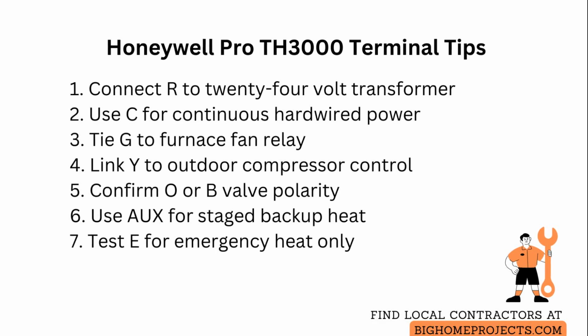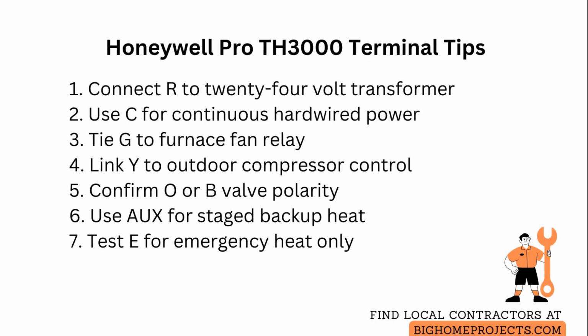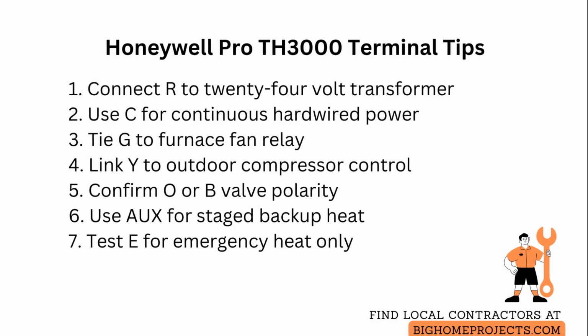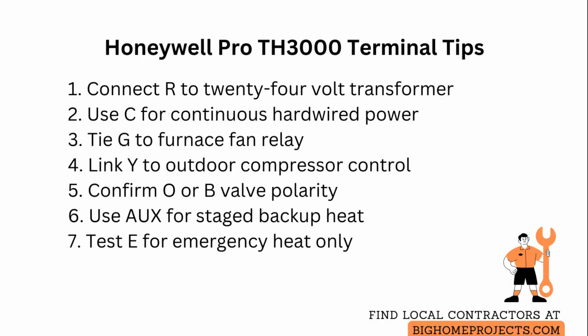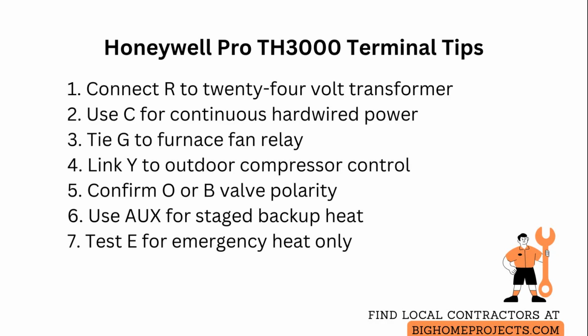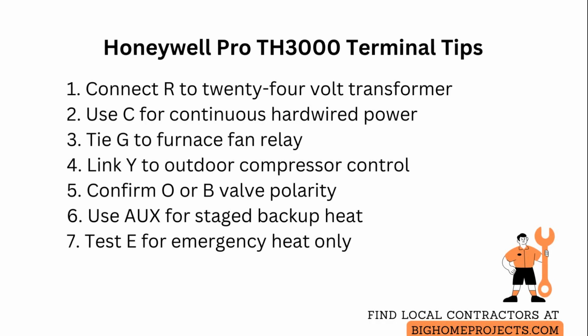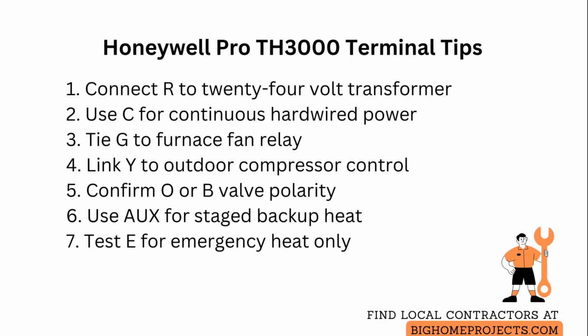The Y terminal operates the compressor contactor for cooling or heat pump stages and should be tied to the outdoor unit control wire. If cooling does not engage, check for continuity and proper relay voltage. The O terminal shifts the reversing valve for most heat pump brands into cooling mode, and the B terminal does the same for some brands like Ruud and Rheem, where it shifts for heating mode, so confirm which valve polarity your system requires before wiring.